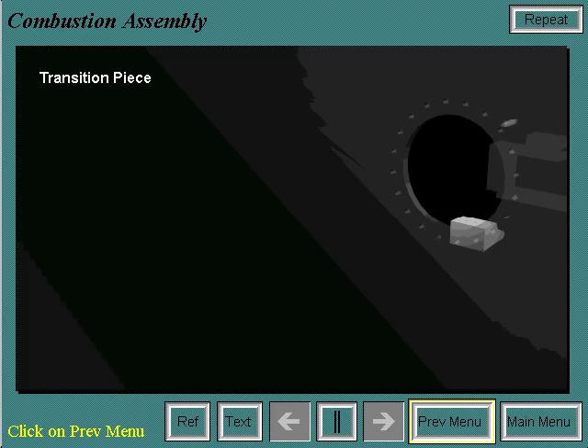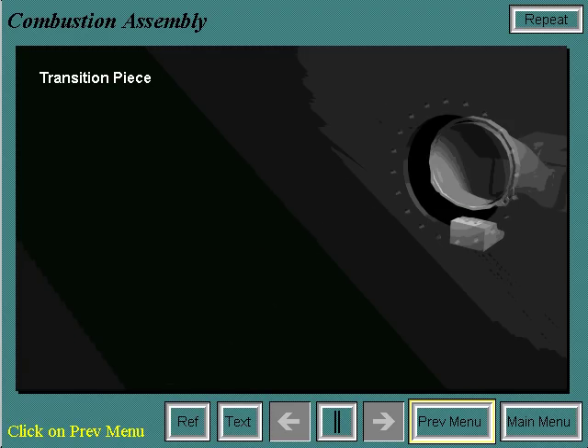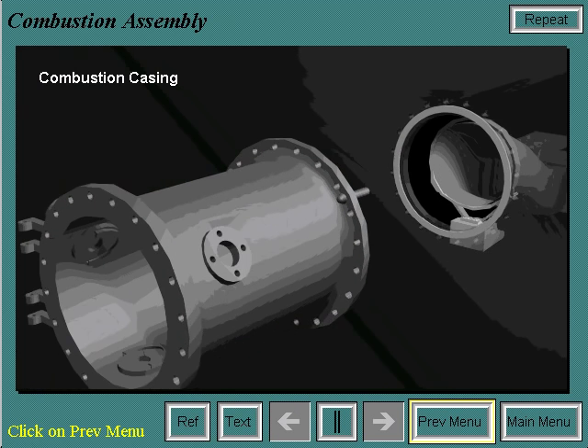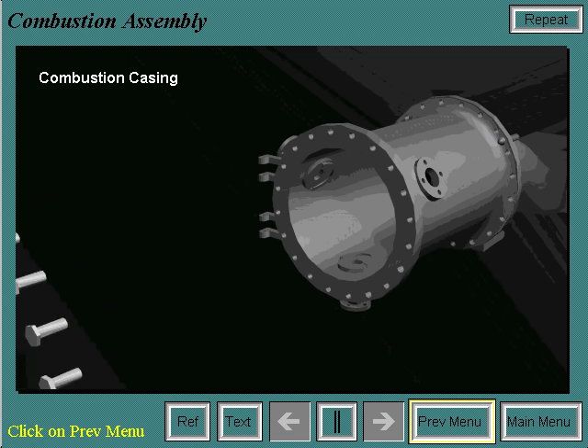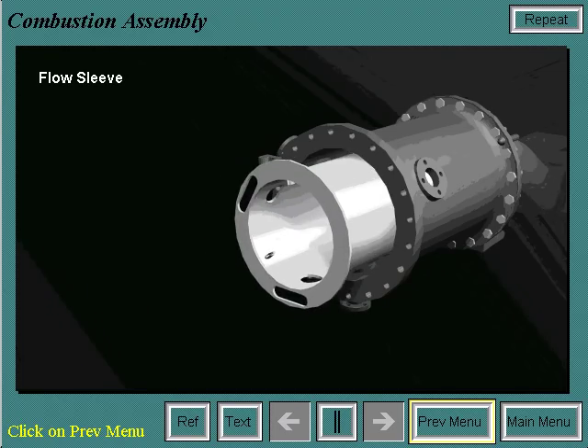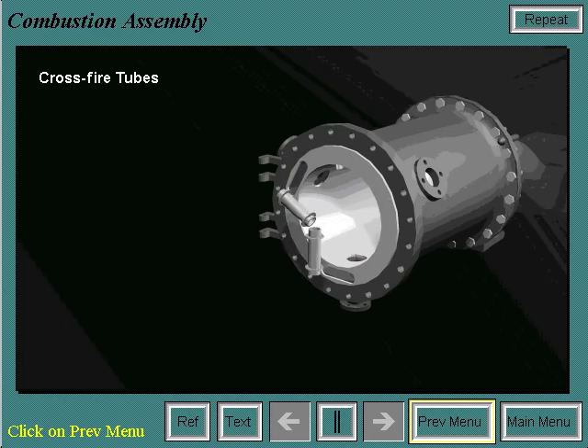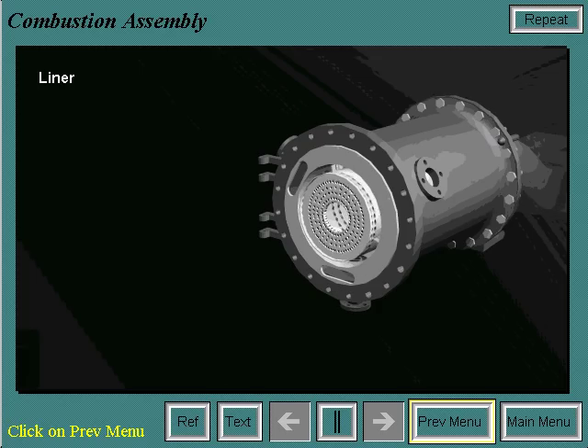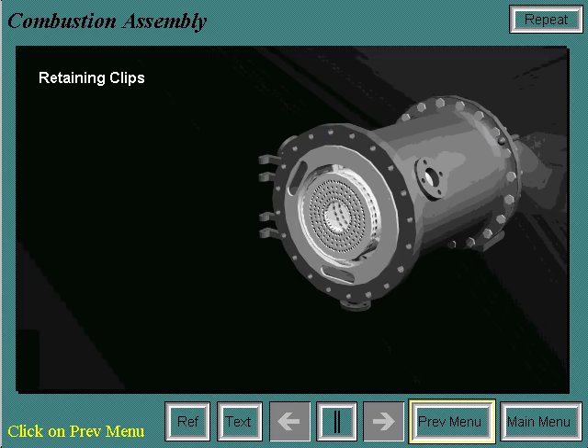The assembly of the combustion system begins with the transition piece bolted to the first stage nozzle on its aft end and supported by the bullhorn bracket on its forward end. Next, the combustion casing is bolted onto the combustion wrapper. Then the flow sleeve slides into the casing. The crossfire tubes are then installed but pushed out of the way so that the liner may be installed. Once it is, the crossfire tubes are put into the crossfire tube collars in the liner, and retaining clips keep them in place.